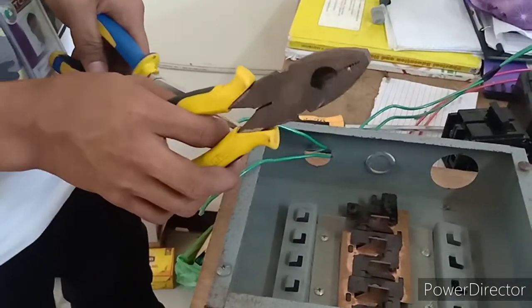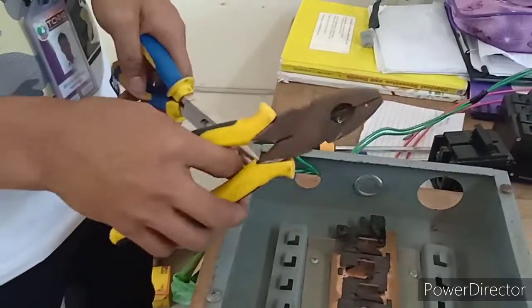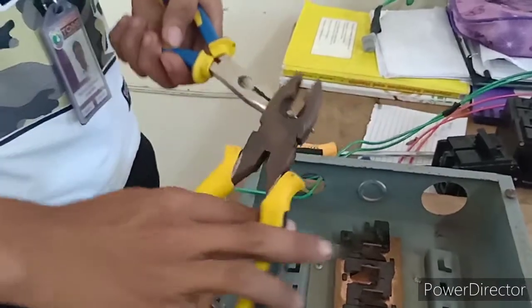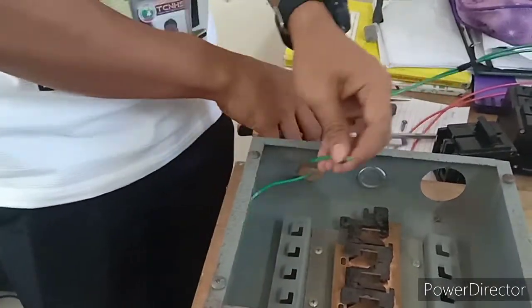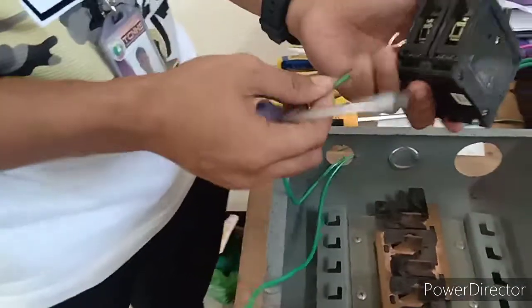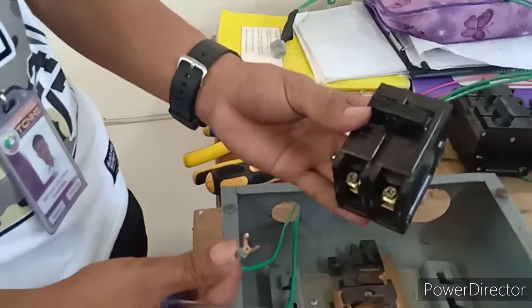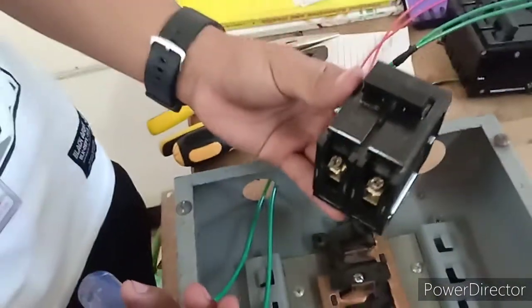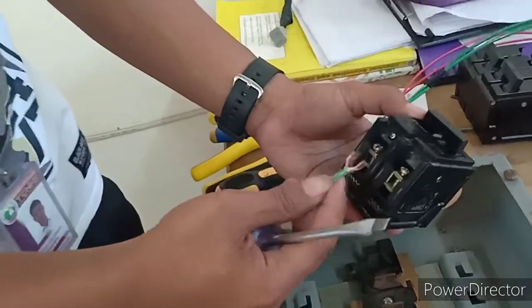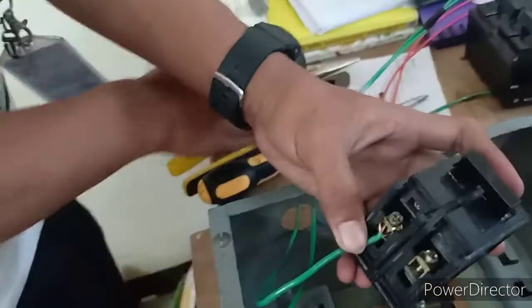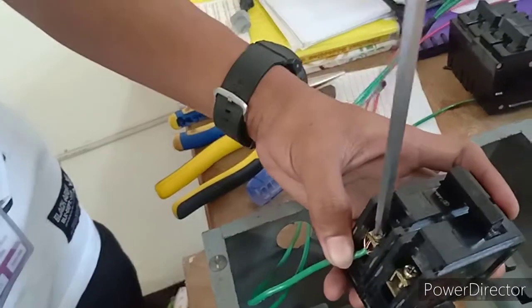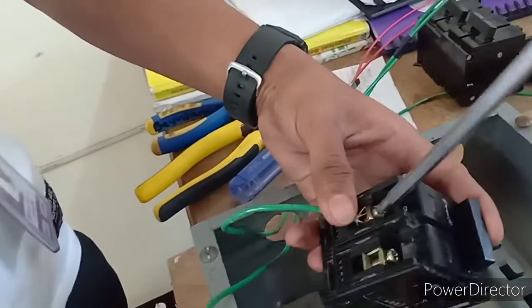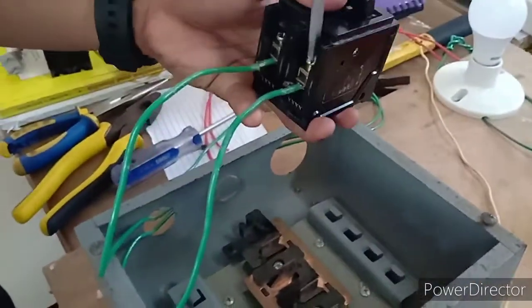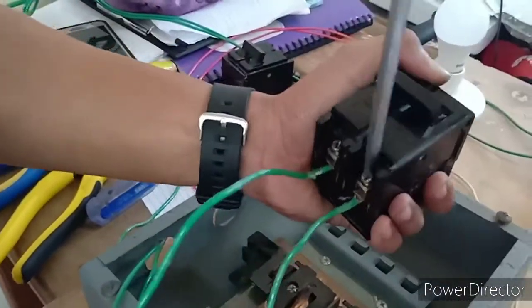So splice first the number 8 service entrance. After splicing, put it on the terminal of the main breaker. So we have the main breaker is 100 ampere. Okay, insert it on the terminal 1. Then tighten the screw bolt using the Phillips screwdriver. Be sure to tighten the screw bolt of the circuit breaker.